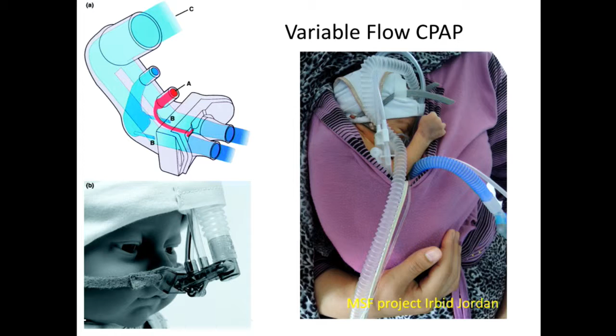Basically, for the bubble CPAP, you need something to give you compressed oxygen and another device to give you compressed air. And then you need to mix the two and have an algorithm or a measurement to see what concentration of inspired oxygen the baby gets. You need to attach it by some means to the baby's nose or to the baby's airways. And then you need to create a pressure on the expiratory part of the system, having a bubble flask with a bubble where you can set a meter on the centimeters of pressure you want the baby to have. It's important to have this on the expiratory limb and not on the inspiratory limb, so as not to increase the dead space of the baby.